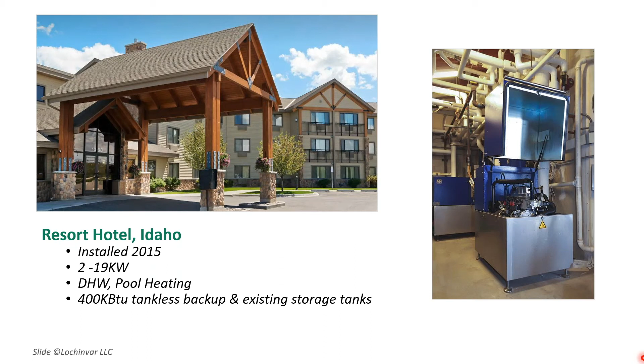In this case, at the hotel in Idaho, they connected a brazed plate heat exchanger to heat their indoor pool overnight. They easily needed to absorb the 40 kW this system was producing, and utilized the heat for pool heating overnight, in addition to filling their storage tanks. Again, the backup heat was there for peak demand. It's just different ways to use this product.